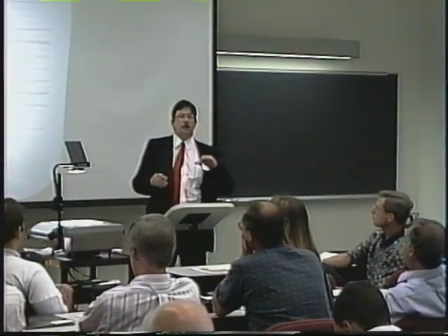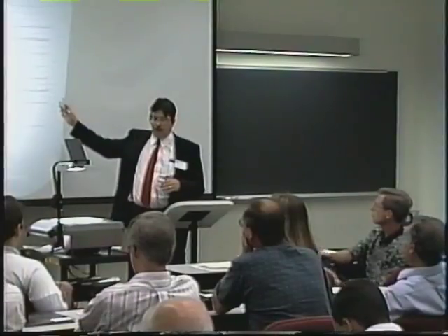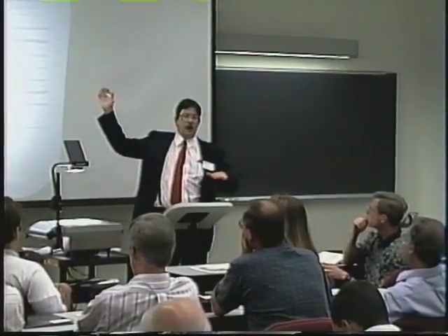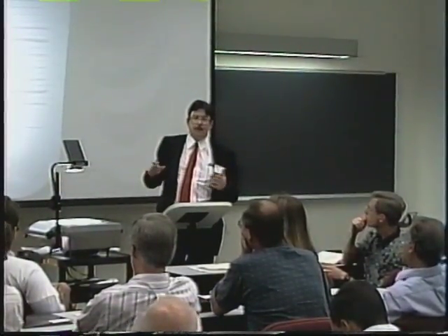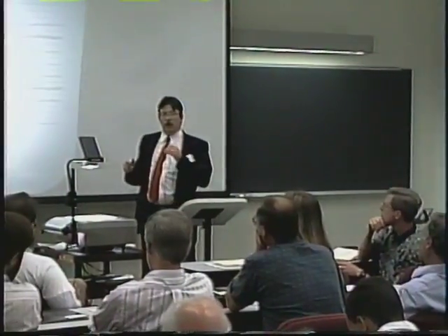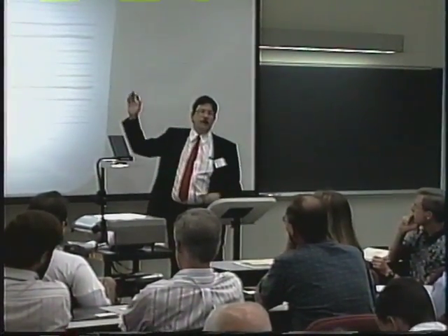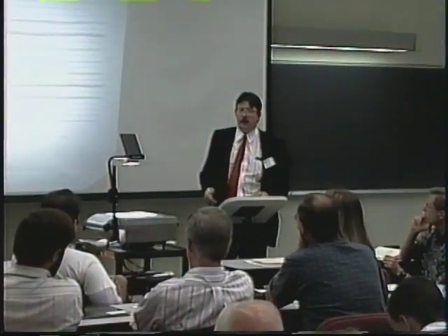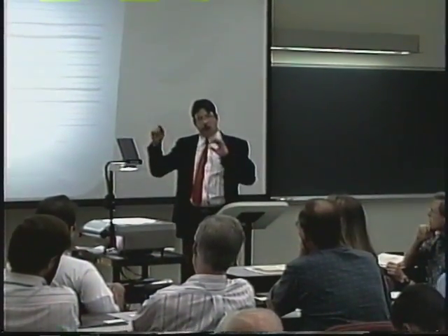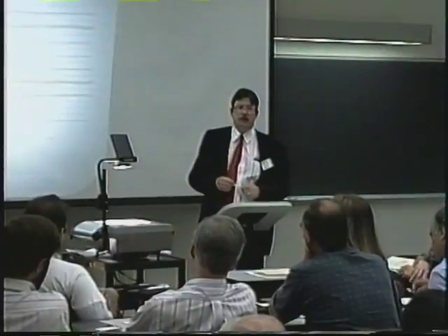So we're using as many different substances as we can. But because of what I showed first, the deviations in the low and high ends of a standard curve due to Beer's law, we require that externals be run in the region of the low end and the region of the high end. The middle is easy to anchor, but in those two areas we want to see that our accuracy is good. And we get as many different materials as we can.